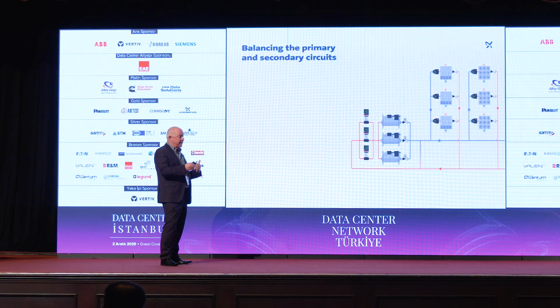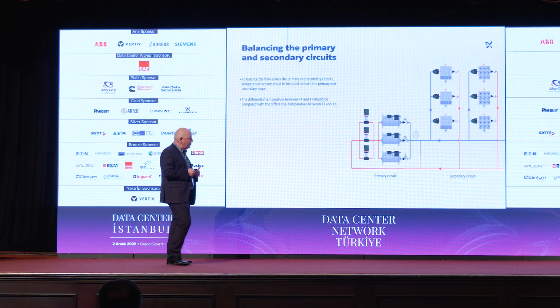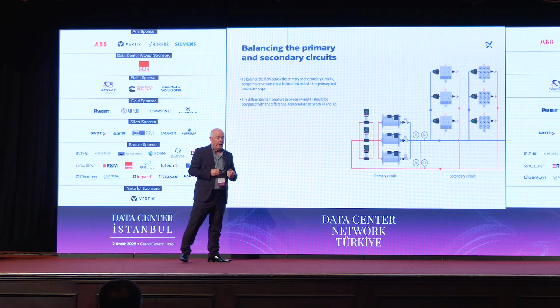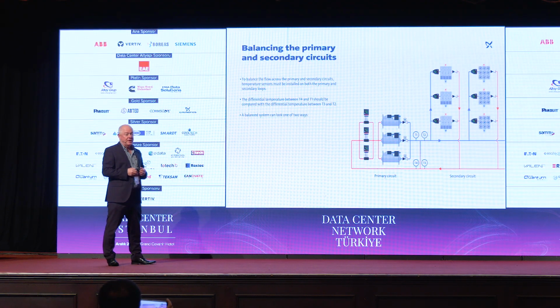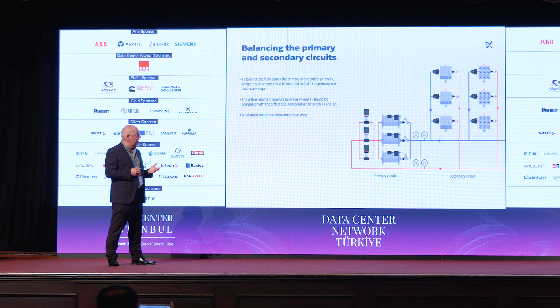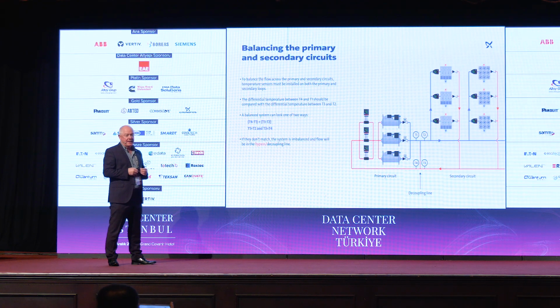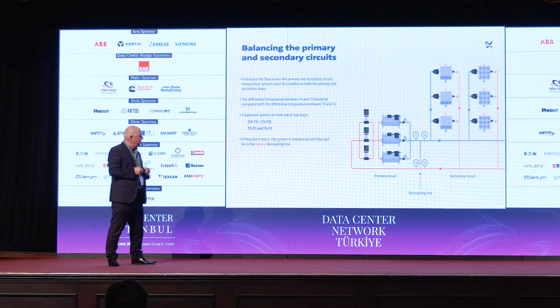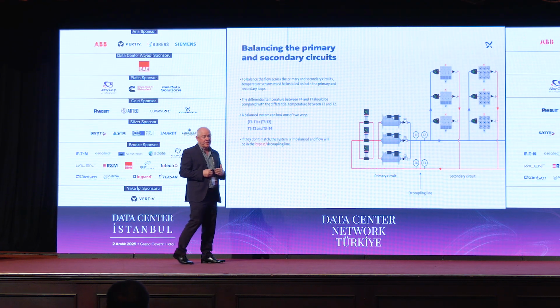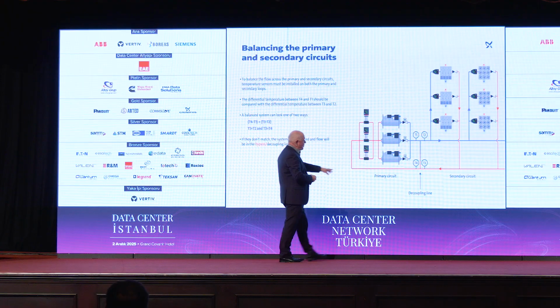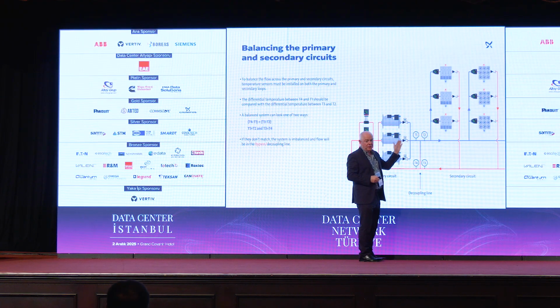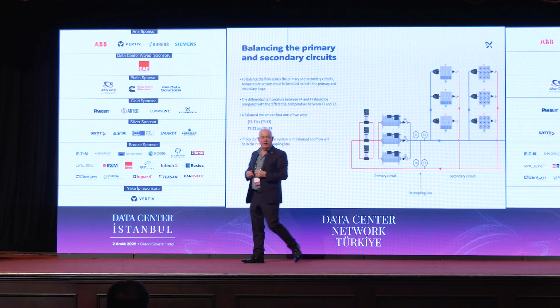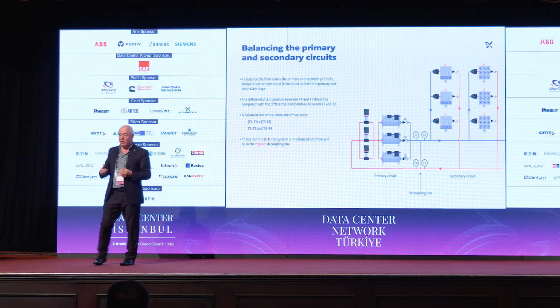And how we link the two systems is quite simple. We put temperature sensors across the decoupling line. T1 should equal T2 and T3 should equal T4. And if that's the case, we have the system in complete balance. We're generating enough liquid to our cooling on the primary side to meet the demand on the secondary side. If the load changes on the secondary side, we will get changes here and the pumps will speed up and slow down to bring it back to equilibrium. And as I said, this is happening in real time all the time.